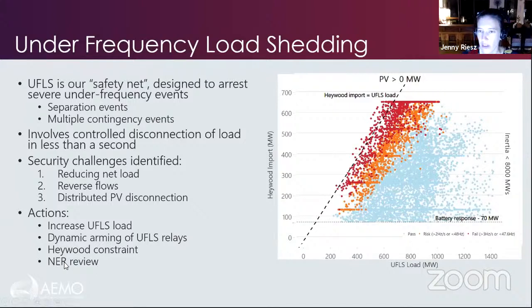And this is one where we've had to review the whole rules framework for how under-frequency load shedding is managed in our grid, because when the rules were developed, no one anticipated that we could see anything like this. So the rules don't make a whole lot of sense in terms of how much under-frequency load shedding we should have and how that emergency frequency response should be supplied.